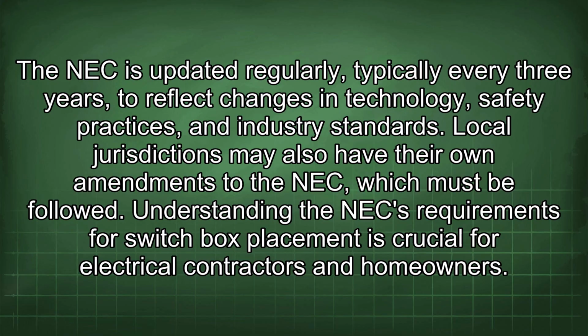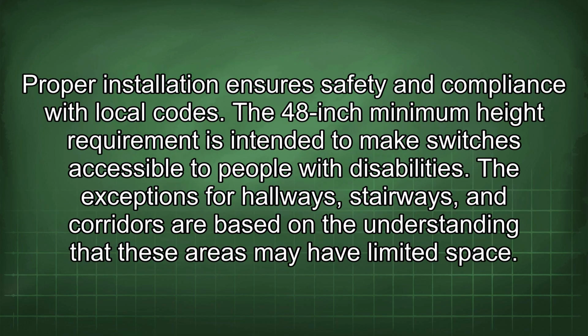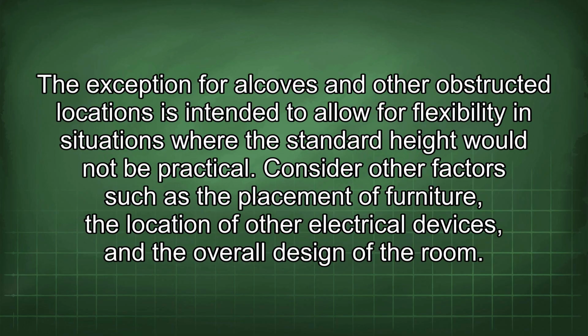Understanding the NEC requirements for switchbox placement is crucial for electrical contractors and homeowners. Proper installation ensures safety and compliance with local codes. The 48-inch minimum height requirement is intended to make switches accessible to people with disabilities. The exceptions for hallways, stairways, and corridors are based on the understanding that these areas may have limited space. The exception for alcoves and other obstructed locations is intended to allow for flexibility in situations where the standard height would not be practical. Consider other factors such as the placement of furniture, the location of other electrical devices, and the overall design of the room.